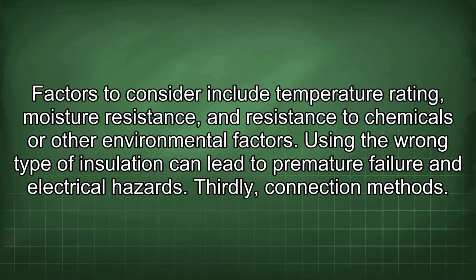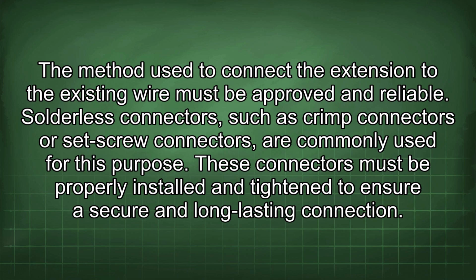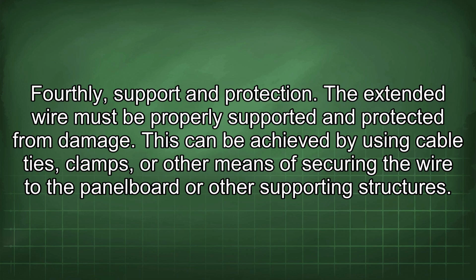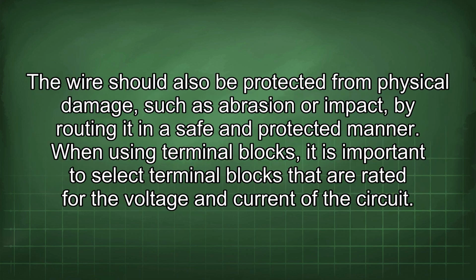Thirdly, connection methods. The method used to connect the extension to the existing wire must be approved and reliable. Solderless connectors, such as crimp connectors or set screw connectors, are commonly used for this purpose. These connectors must be properly installed and tightened to ensure a secure and long-lasting connection. Fourthly, support and protection. The extended wire must be properly supported and protected from damage. This can be achieved by using cable ties, clamps, or other means of securing the wire to the panel board or other supporting structures. The wire should also be protected from physical damage, such as abrasion or impact, by routing it in a safe and protected manner.